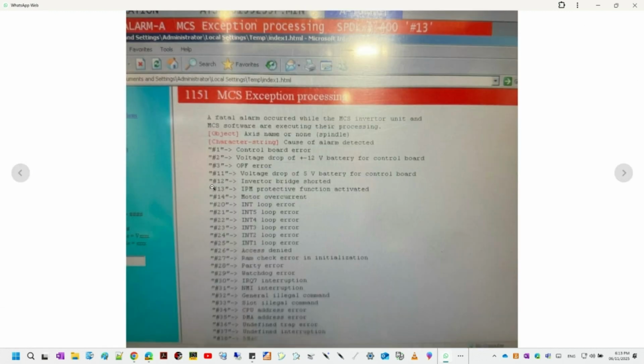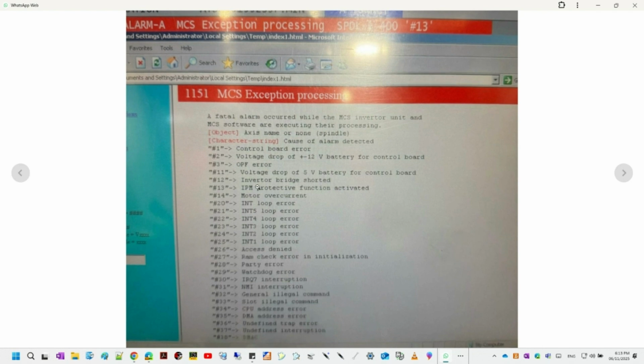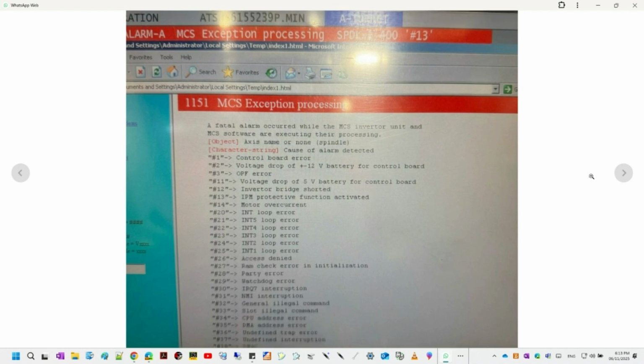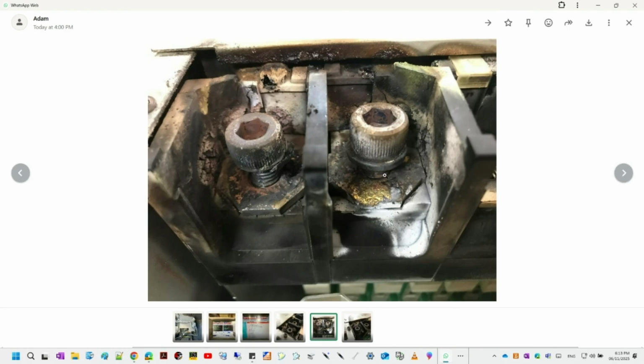Right, compounding the problem. And of course, the damaged insulation on the cables themselves, it was burnt, cracked, brittle, just destroyed from the extreme temperatures involved. And all of this visual evidence, taken together, strongly suggested one primary cause. Yeah, based on those really distinct signs, the localized heat, the melting, the arcing right at the terminals, the probable cause they identified was a high-resistance connection. And the most common reason for a high-resistance connection on something heavy-duty like this, like what actually causes that high resistance? By far, the most common reason is just loose terminal bolts.